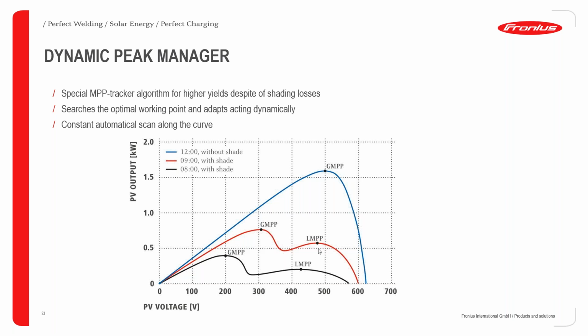So for the Dynamic Peak Manager, what it does is automatically scan along the production curve, and if there is any shading, it detects and aligns itself to the highest power production point, as we can see here. So instead of producing at the LMPP, which is the local MPP point, it now automatically, through the scanning, shifts to the GMPP, which is the global MPP, and then produces power on that particular setting. As you can see, it automatically adjusts the voltage, which corresponds to a change in current. And of course, this leads to a higher output power.